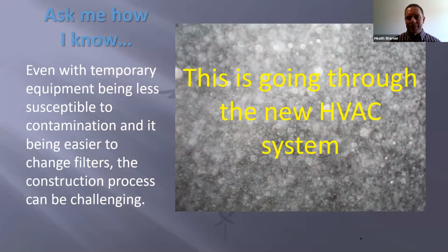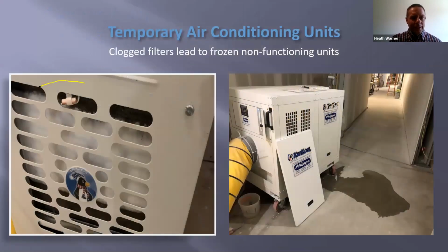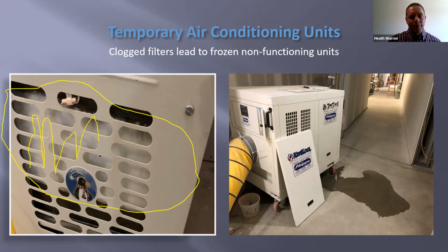Picture on the right, dust particulates, every job site, especially when you get to the drywall phase and dusting and grinding and everything else that goes along with it. The picture that you see on the left, this is a 1.1 ton temporary air conditioner. That 1.1 ton temporary air conditioner should have a coil set that looks about like the radiator of your car, which we're all very familiar with. You don't see that. What you do see is a solid chunk of ice. Somebody decided that they should probably try to save $6 on a pre-filter and try to run a temporary air conditioner without any filter. Eventually, during the drywall phase, coils all clogged up, had a solid chunk of ice. Took about 4 hours to clean that unit out just to get the coil set back up and running.